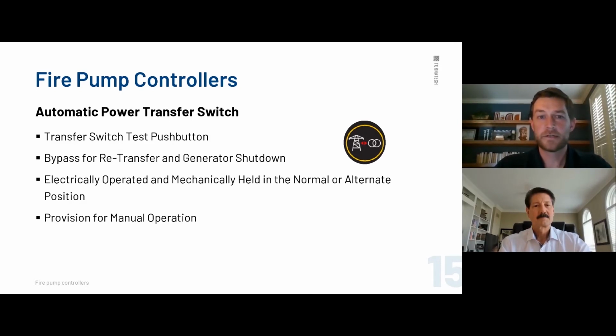Okay, the generator, we've got a transfer switch test button. You can see this icon right here. If you have a panel that has the automatic transfer switch, you're going to have this button on there. That button is used to test. When you press it, it's going to send a signal to start the generator. It's going to transfer power once the generator voltage has gotten up to the healthy voltage it needs to make the transfer. And it's going to run, I believe it's a 5-minute test, before it will switch back to normal power. Those are all field adjustable as well.